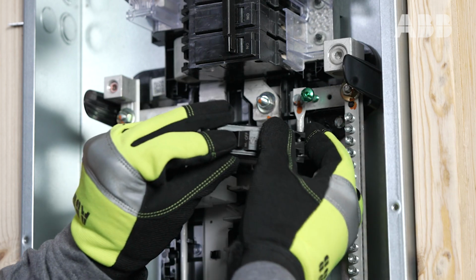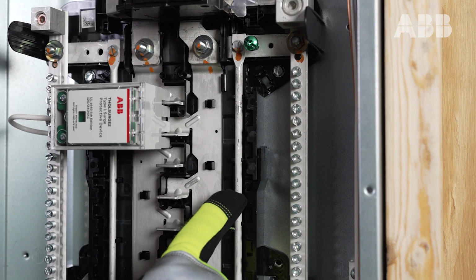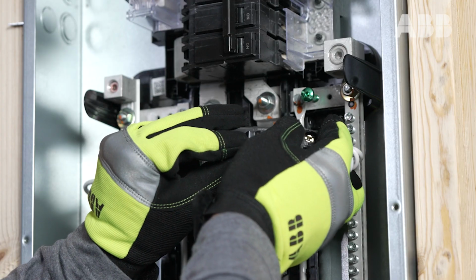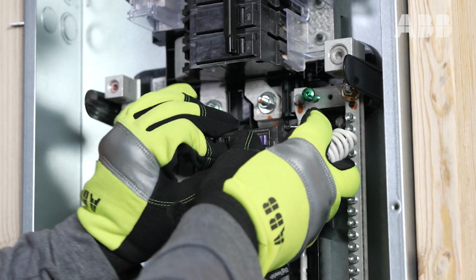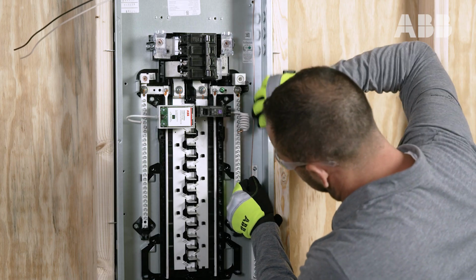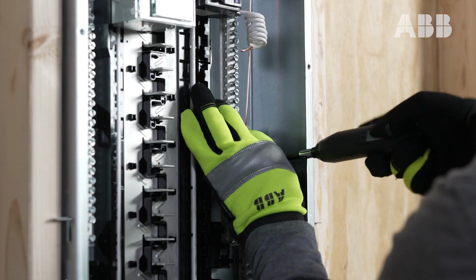Install the heel of the circuit breaker into the load center mounting rails and rotate the top part of the circuit breaker to connect with the bus bar. Connect the ground wire to the ground bus bar.